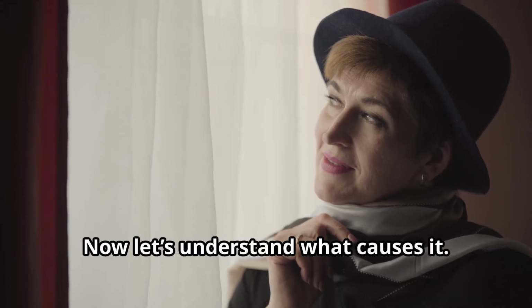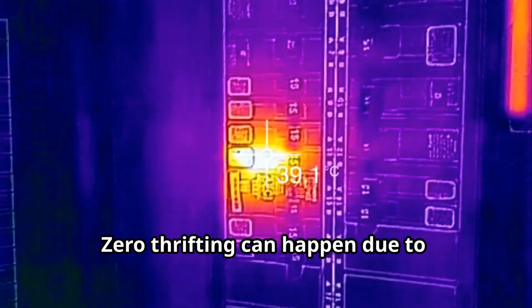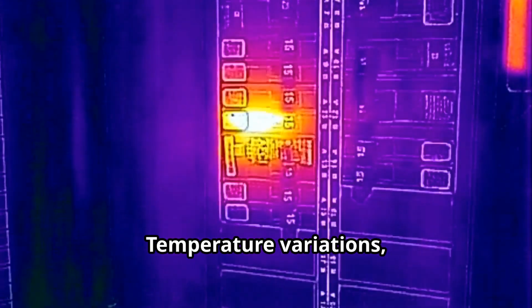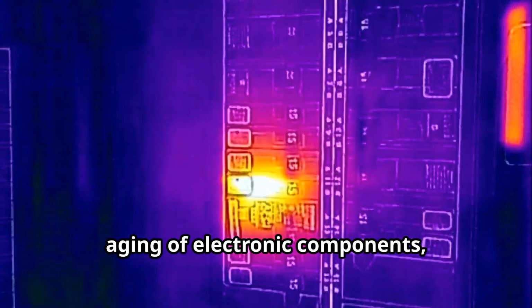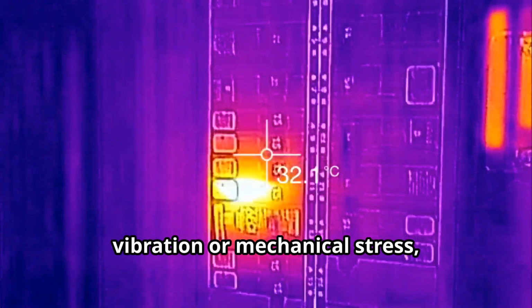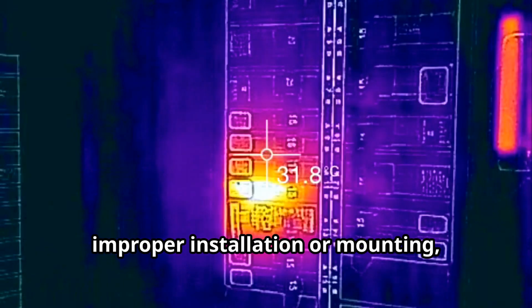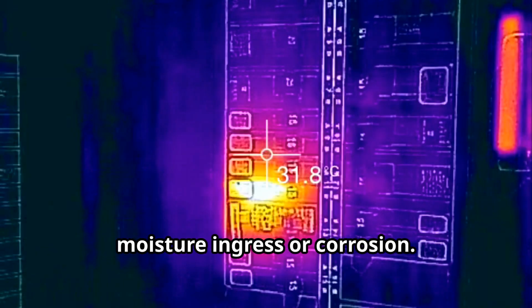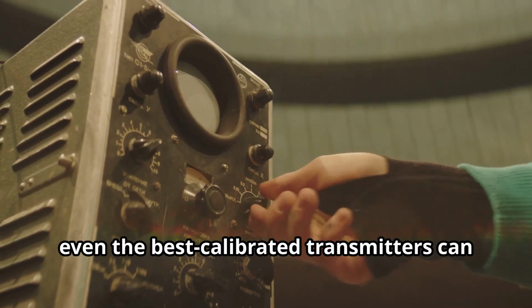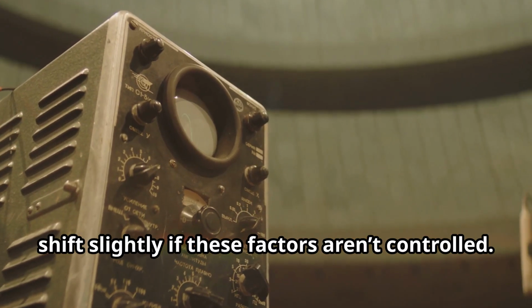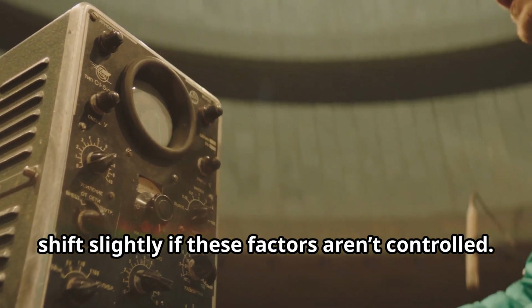Now let's understand what causes it. Zero drift can happen due to temperature variations, aging of electronic components, vibration or mechanical stress, improper installation or mounting, moisture ingress or corrosion. Over time, even the best calibrated transmitters can shift slightly if these factors aren't controlled.